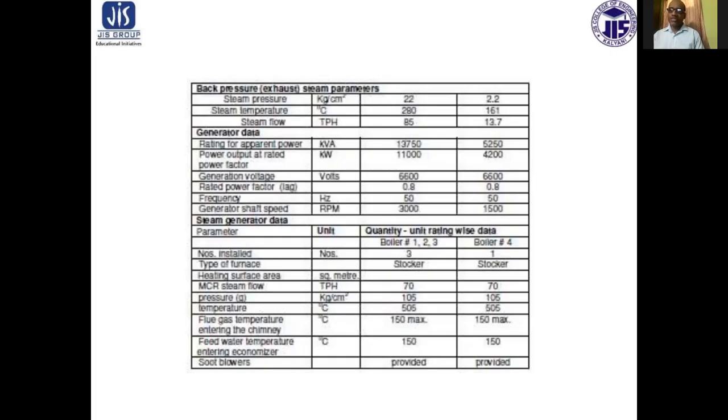The generator data: apparent power rating is 13,750 kVA for the 11,000 kW sets and 5,250 kVA for the second extraction cum back pressure turbine set. Generation voltage is the same at 6,600 volts, power factor 0.8, frequency 50 Hertz, and generator shaft speed 3,000 RPM.